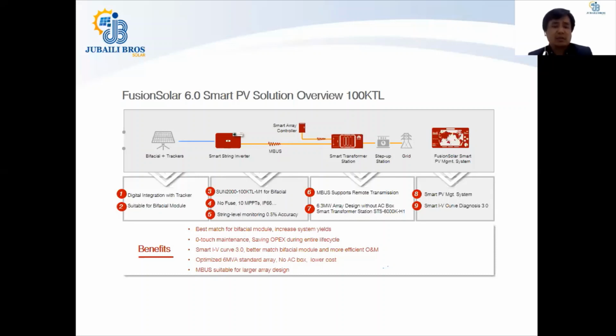It uses no fuse because it is again made with the philosophy of two strings per MPPT, and it has high accuracy of measuring string-level voltage and current, which you can monitor on your FusionSolar platform. You see exactly what each of your strings is generating in terms of voltage and current, and that can also give you ample information on which string is abnormal and which string is functioning normally.